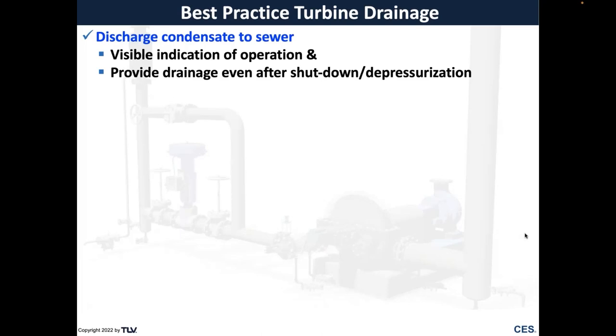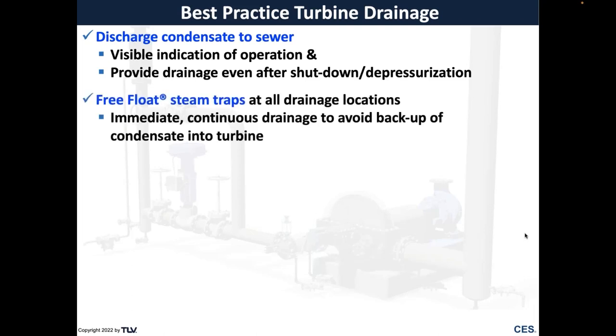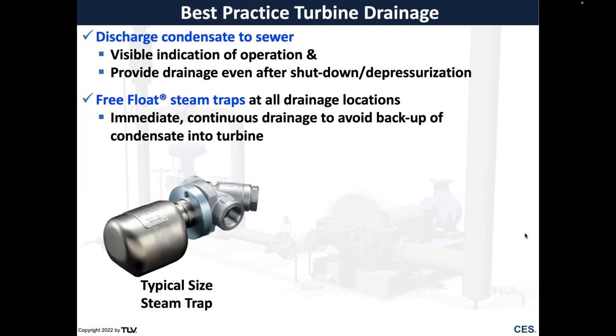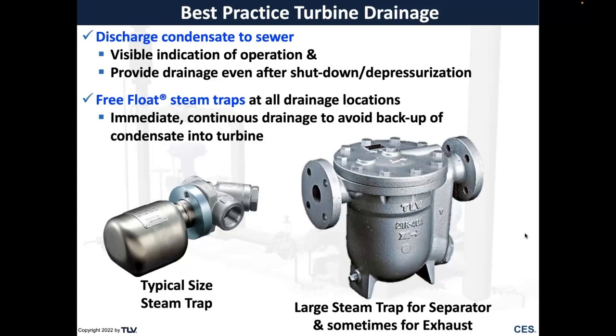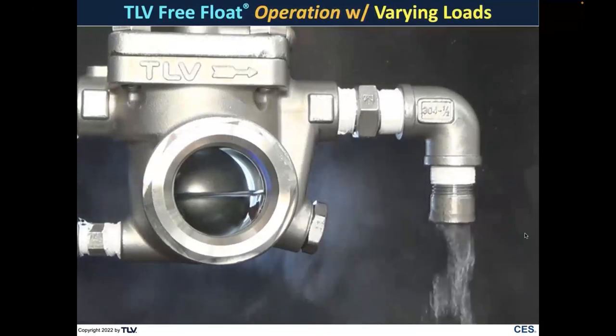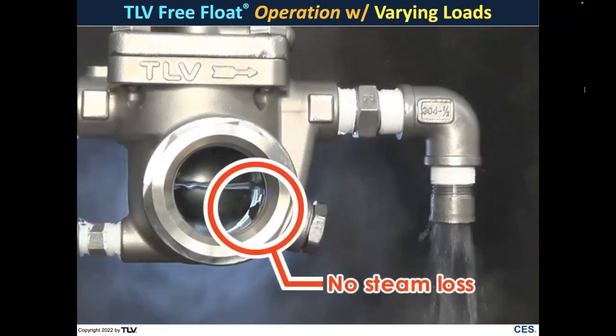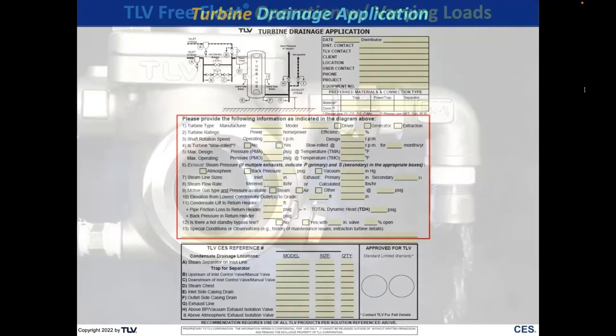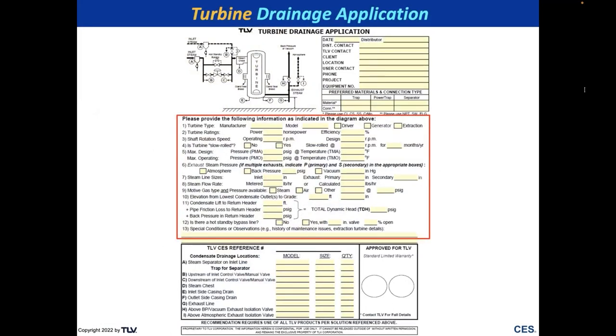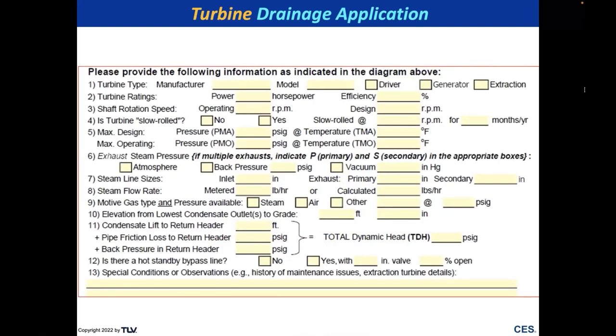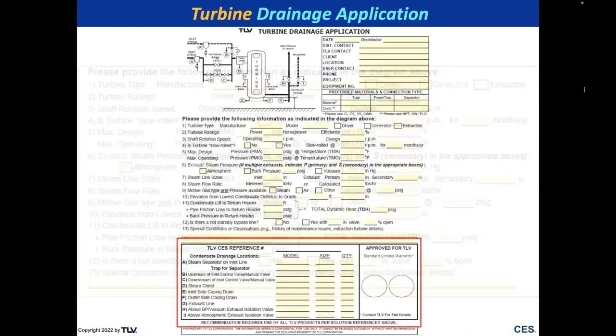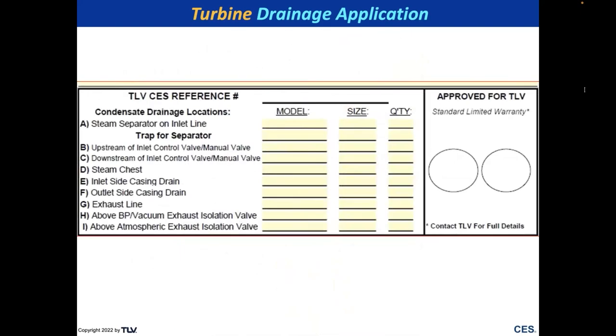For turbines, discharge condensate to the sewer for visible indication of operation and drainage after shutdown and depressurization — especially if manual open is not performed. We prefer Free Float® traps for immediate, continuous drainage to avoid condensate backup into the turbine. The free float keeps a water seal and responds instantaneously, which is why we use free-float drain traps. For every turbine application, we complete a TDA (Turbine Drainage Application) form — the customer fills in key data and we make model selections, typically at no charge.